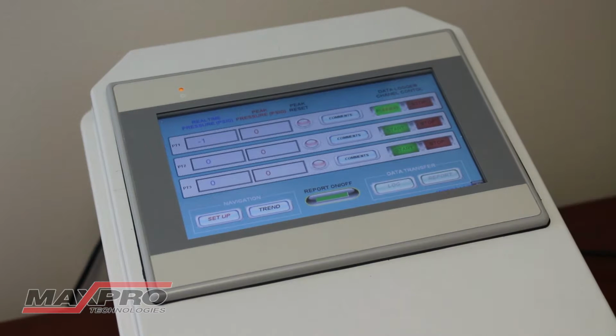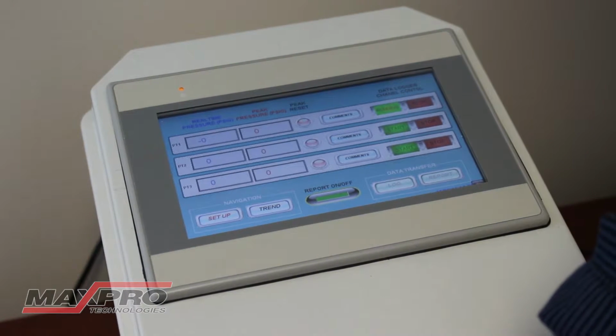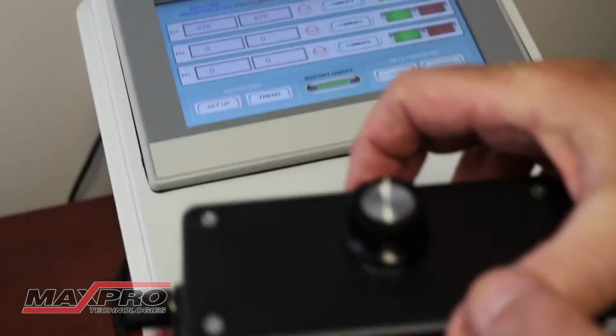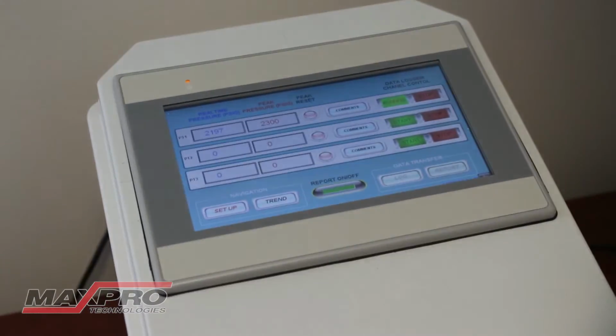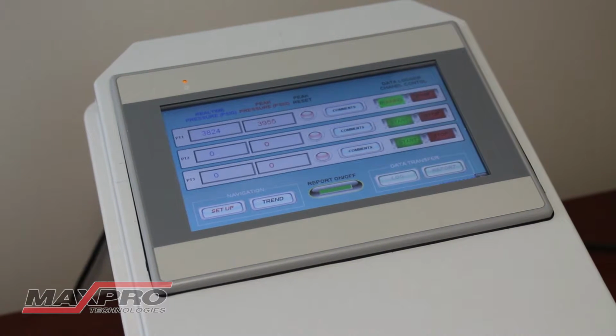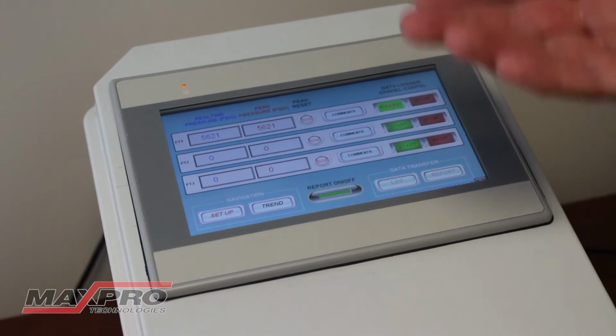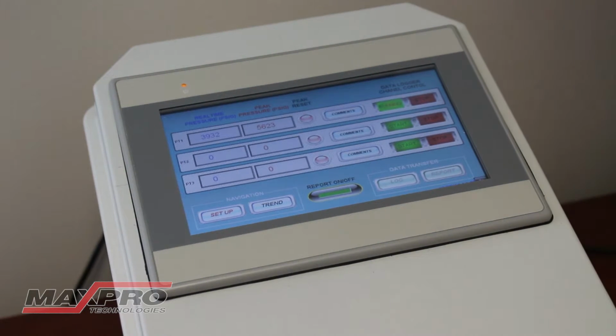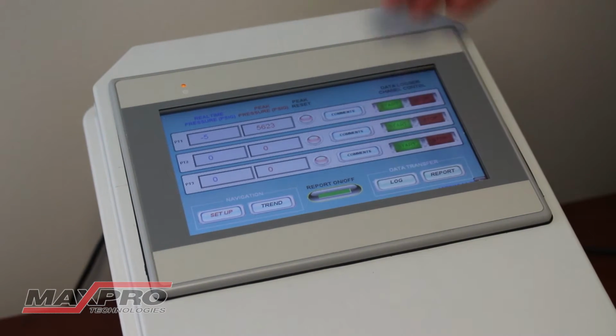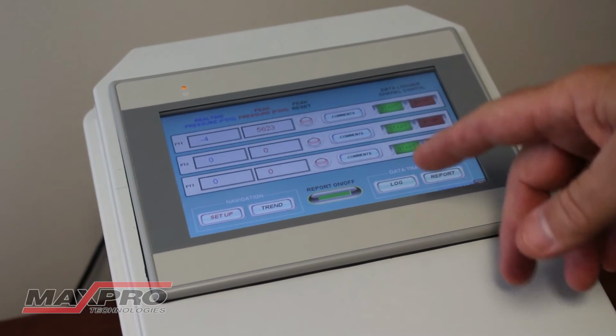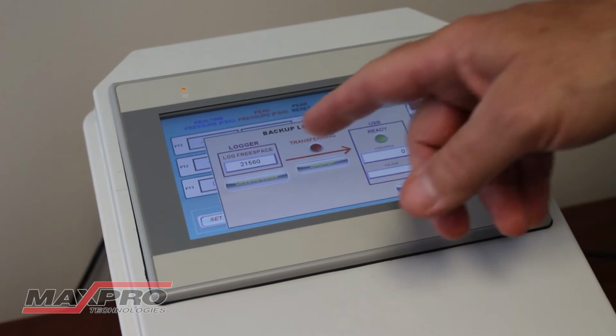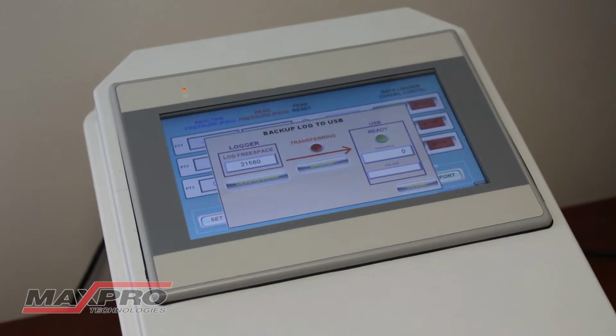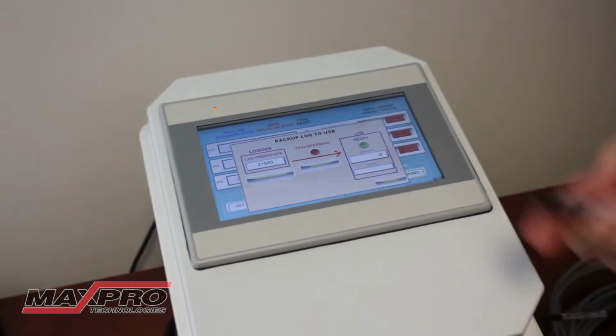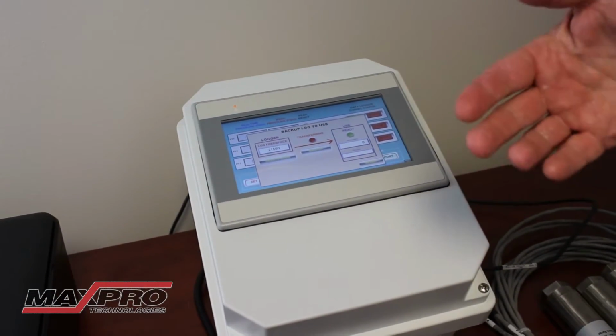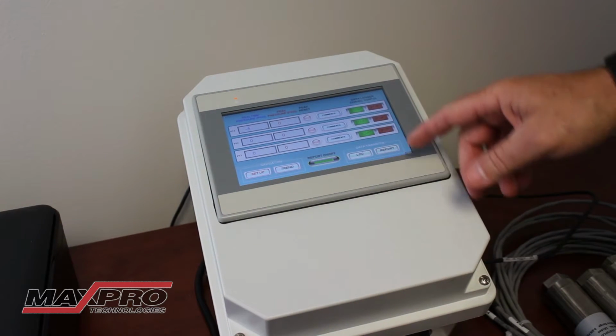Now it says it's running, so your test is running. What we have here now is just a simulator to simulate a pressure test. So we can take it up in pressure, simulating that there's pressure on the transducer. You'll take it up to pressure, dwell, vent down, and at that point your test is done, so you can go in and hit the stop button on the transducer that you're working with, and then you can either transfer the data from the unit here to a jump drive that's located on the side of the unit, and then you can take that to your computer to store your data. Or you can choose to print out a test report.